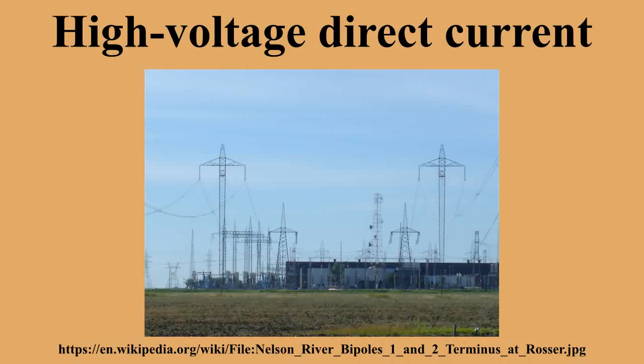Therefore, for the same conductor losses, a given conductor can carry more current to the load when operating with HVDC than AC. Finally, depending upon the environmental conditions and the performance of overhead line insulation operating with HVDC, it may be possible for a given transmission line to operate with a constant HVDC voltage that is approximately the same as the peak AC voltage for which it is designed and insulated. The power delivered in an AC system is defined by the root mean square of an AC voltage, but RMS is only about 71% of the peak voltage.